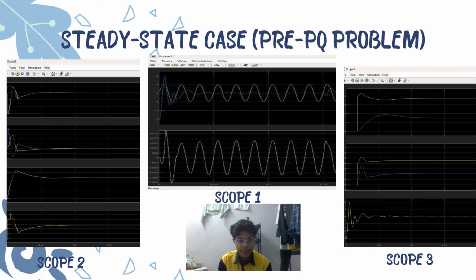For the steady state case, in its initial state, the system is functioning at normal load with no modulation. The variable load remains constant and the distribution STATCOM operates in floating mode. The programmable voltage source is also used to regulate the voltage step, which we need to evaluate the distribution STATCOM reaction. The purpose is to see how the system is stabilized when the distribution STATCOM does not yet mitigate the flicker, and also to see how it responds to the change of the voltage.